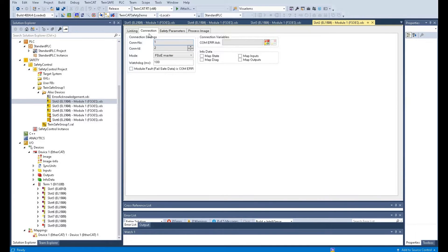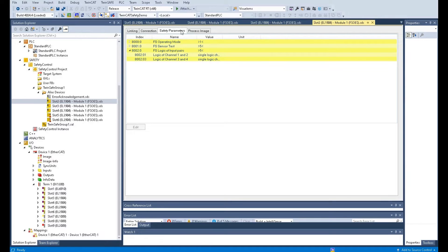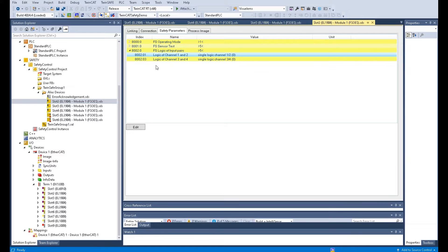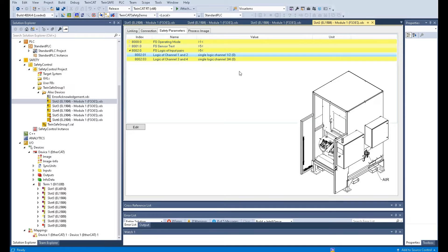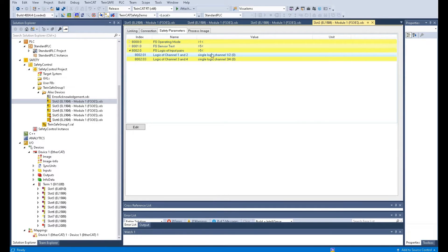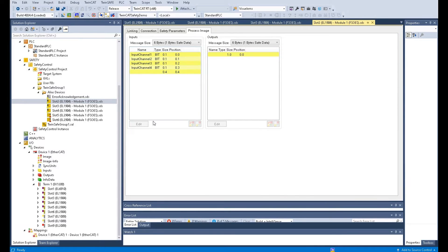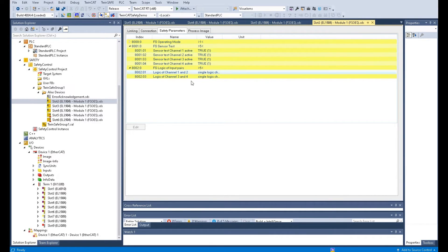The second page is the connection settings. Basically we won't touch this area unless you want to shrink the watchdog to make the system a little bit more sensitive. The one important setting is the safety parameters. According to different applications — for example the e-stop button, the light curtain with OSSD, or the gate switch with OSSD devices with or without test signal — we need to set different settings here. Usually different brands of safety cards have different styles. We will use this cell as an example to show how to set the parameters. For the fourth tab it shows the message size, and we leave everything as default.